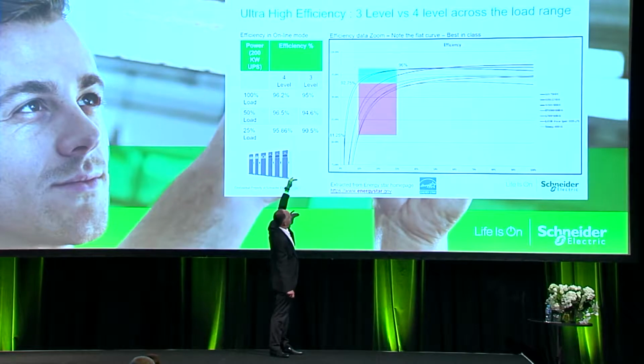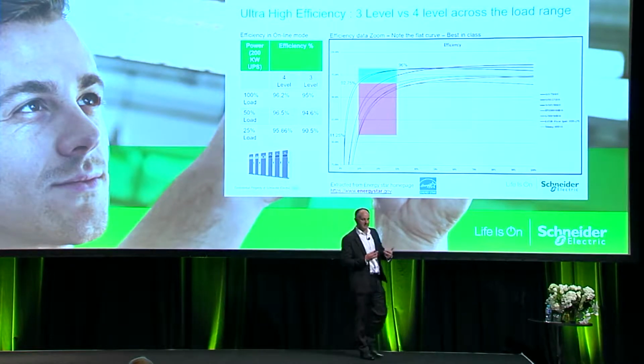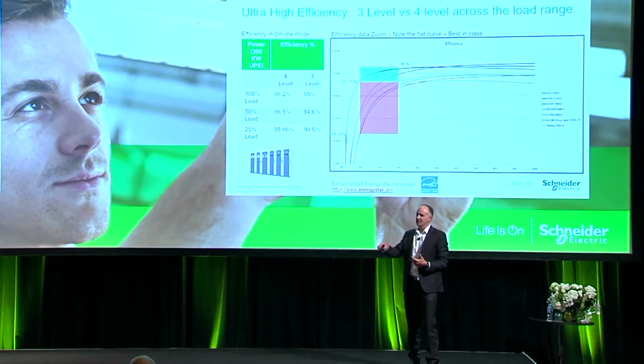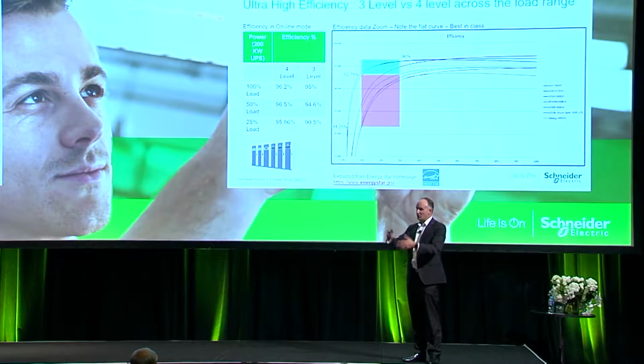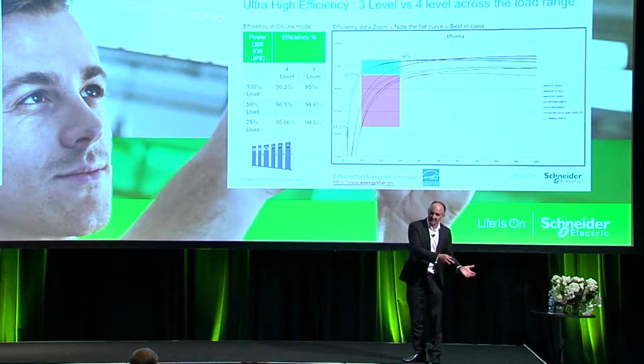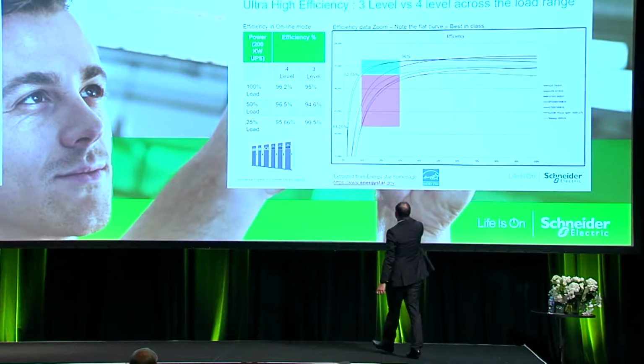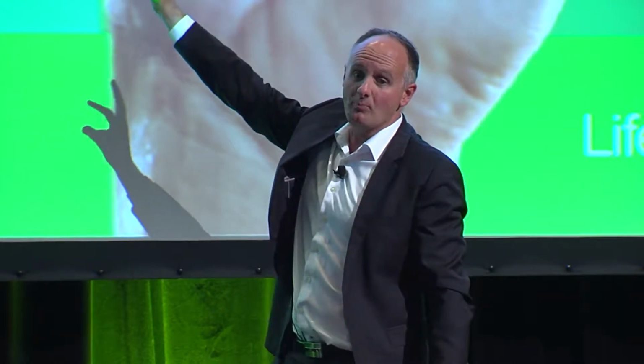So here we compare the current generation UPS, which is the 3-level system, with the new 4-level. So you can see at 100% load, 95% efficient for a 3-level, 96.2 for the 4-level, right? But where it makes a real difference is actually down in this part. So this graph here shows across the bottom percentage loading on the UPS, and then up the side is the efficiency. And you can see that particularly in data center applications where we're operating with high redundancy levels, so we're typically producing 2N architectures with dual bus arrangements, and then particularly during the start of the life of a data center where it's not uncommon to see UPSs really running down in this very low end part of the curve. And that's where we're getting a full 5% or better improvement. So there's a real focus on that low level thing.